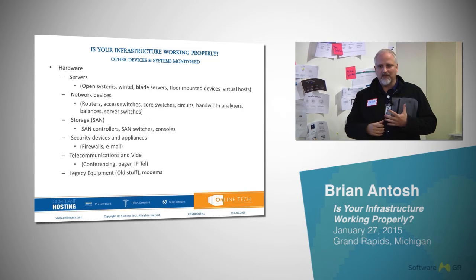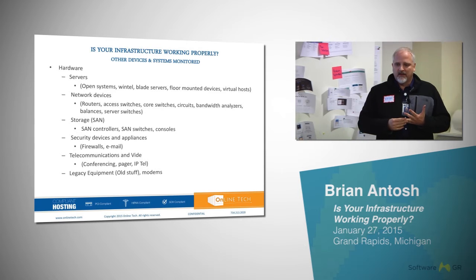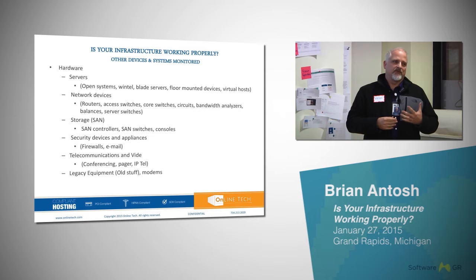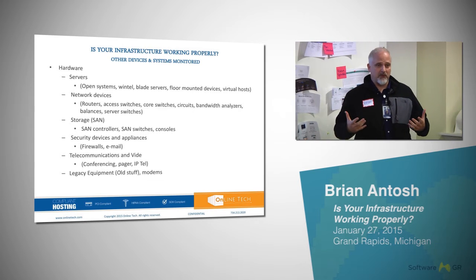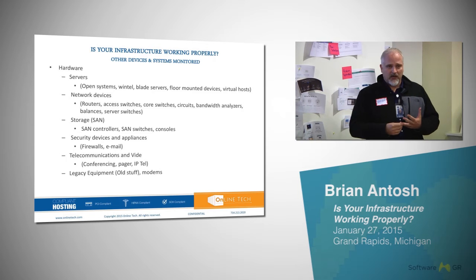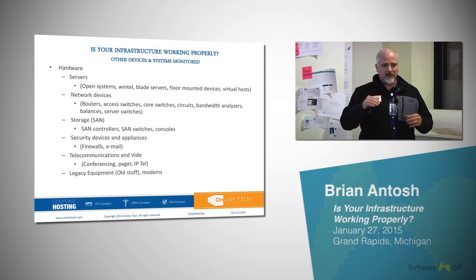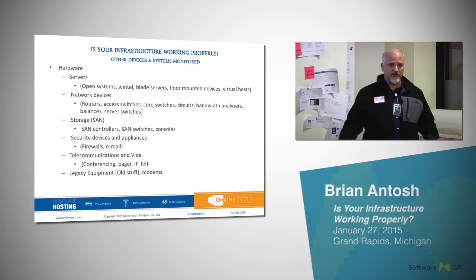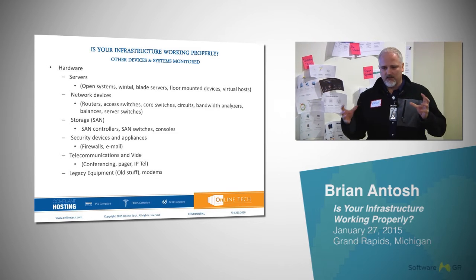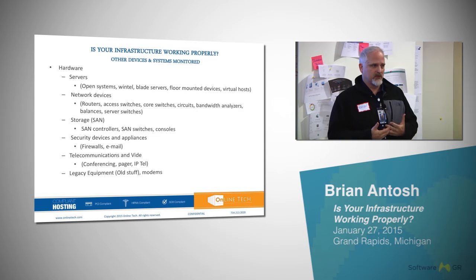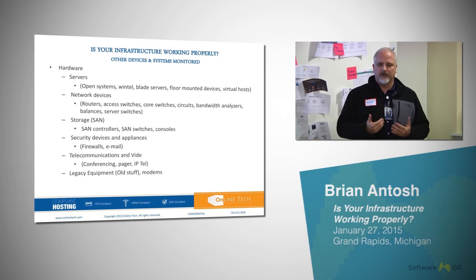So that's some of the highest density devices that I've seen on the floor. And you really get into a big problem of cooling something like that. You have to go to supplemental high density cooling to do it properly and efficiently. Up to about 6 or 7 kilowatts a rack, you can do traditional cooling, under the floor. Beyond that, the efficiency just nosedives. And everything's just getting more dense, so high density cooling is really becoming a big thing to do that properly.